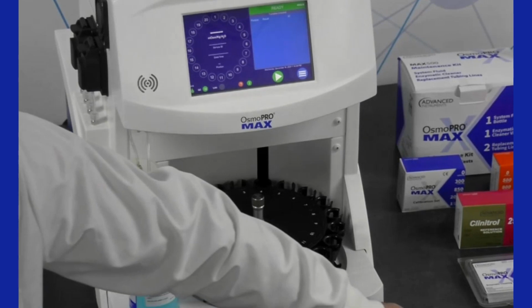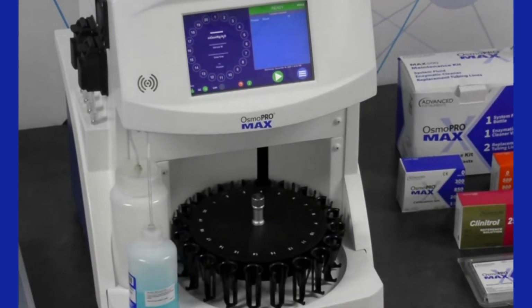Hidden over here on the side is a USB input on this side of the instrument. That's for exporting results. The instrument stores up to 1,000 results and 10,000 events, and all of that result, QC, and event data is exportable manually through the side of the instrument. But that QC data is also exportable remotely to our advanced QC peer group website, which allows you to upload, analyze your QC data, and compare it with the performance of your peers as well. So kind of a fun feature there that makes things easier from a QC standpoint.